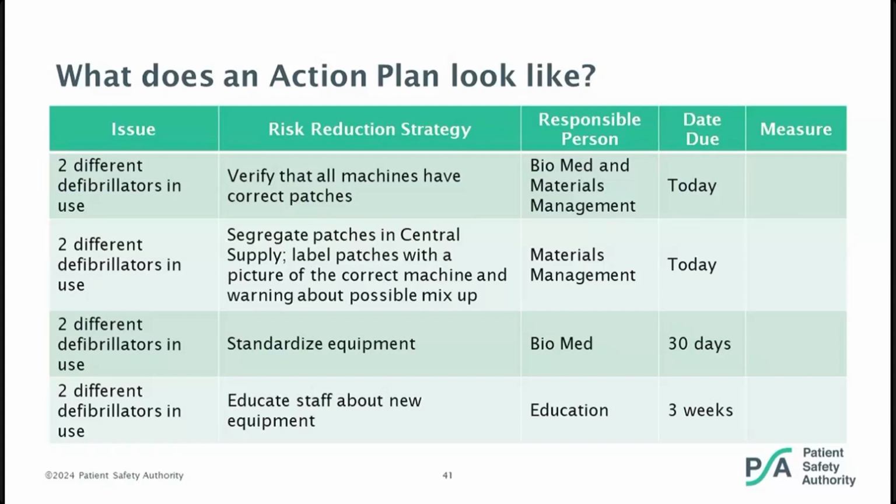The issue, again, 2 different defibrillators. So our risk reduction strategy is going to be segregate patches in central supply, label patches with a picture of the correct machine and warning about the possible mix-up. And material management's going to handle that, and they're going to do that today also.